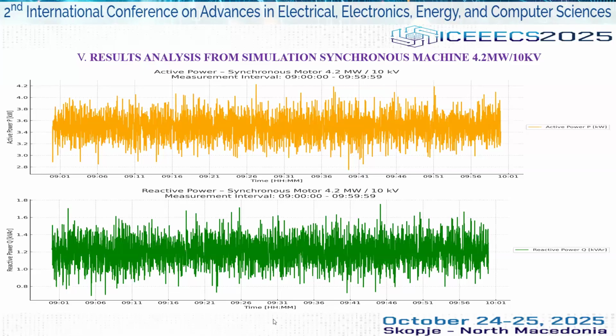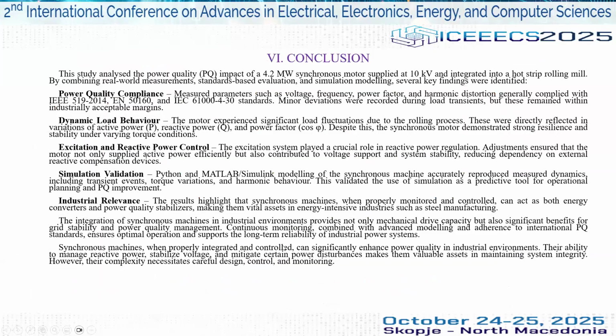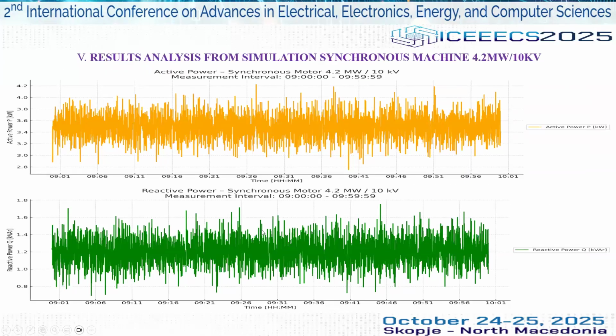The last picture is the reactive power. It highlights the compensation variation of the synchronous motor. The observed fluctuations reflect the adjustment of excitation to the dynamic rolling mill regime. This confirms the essential role of the machine in maintaining voltage stability and keeping the power factor within accepted limits.